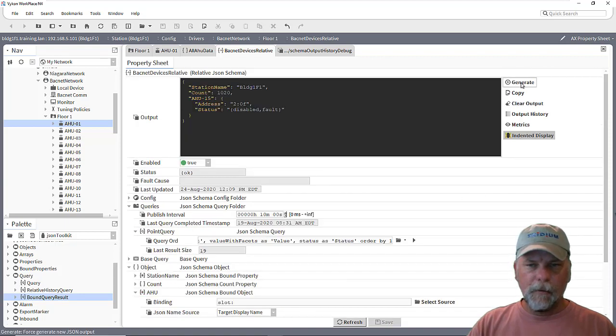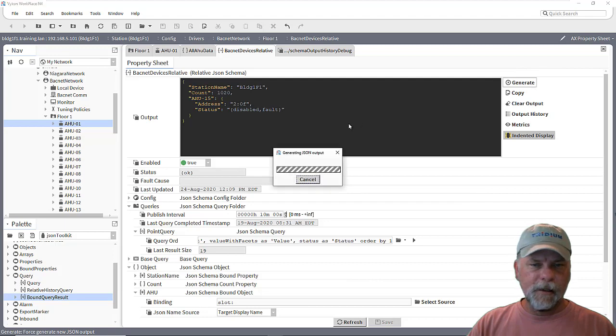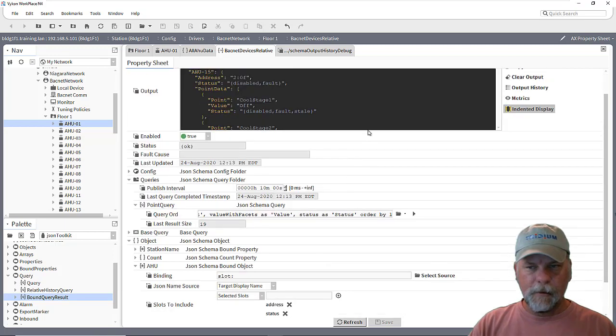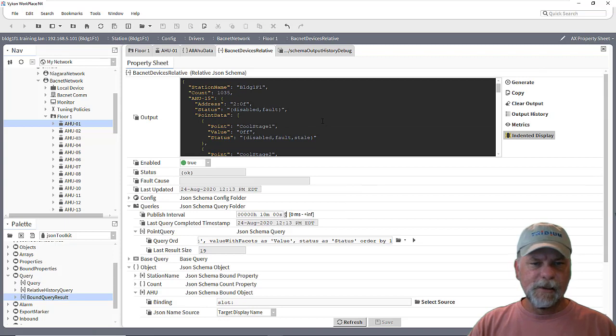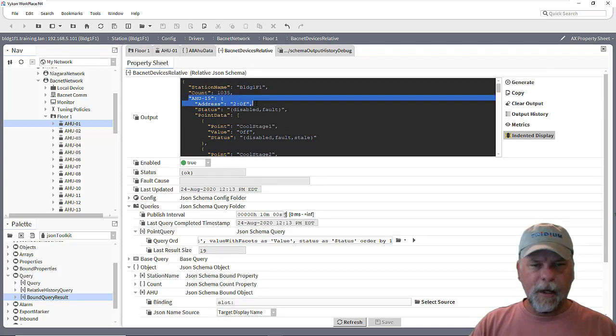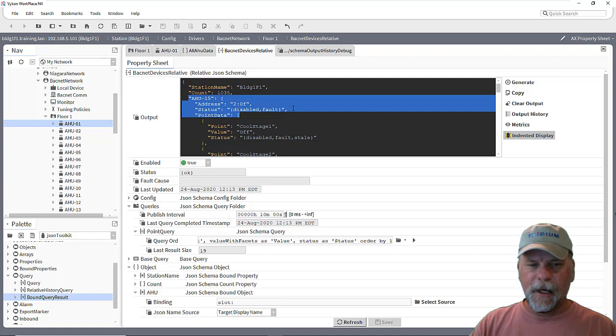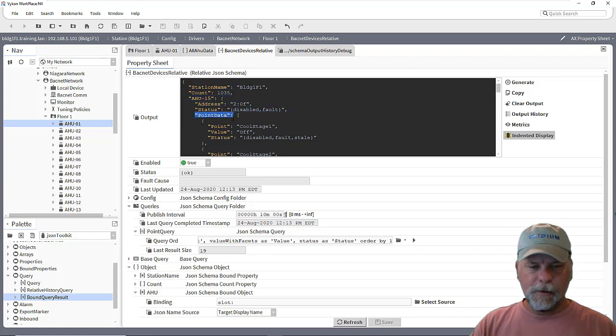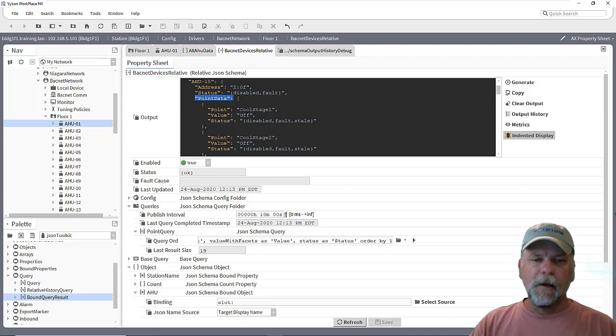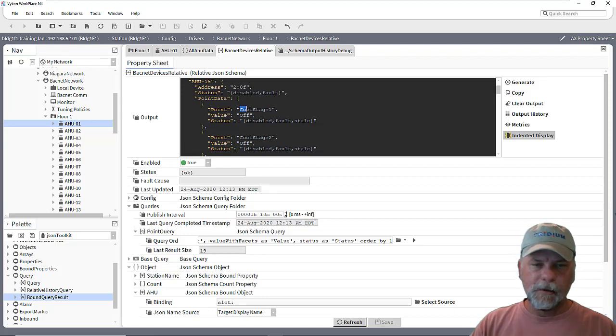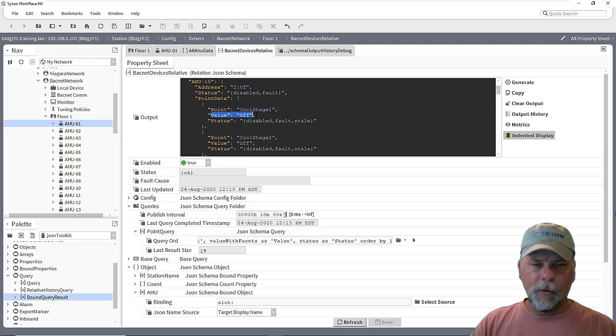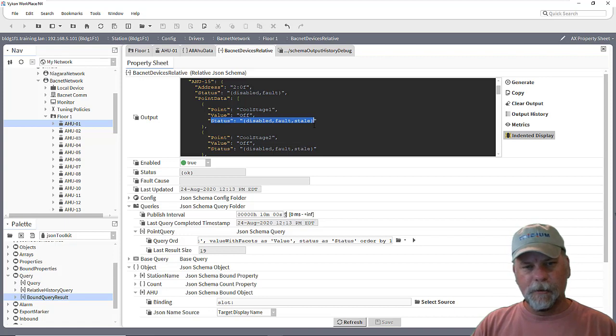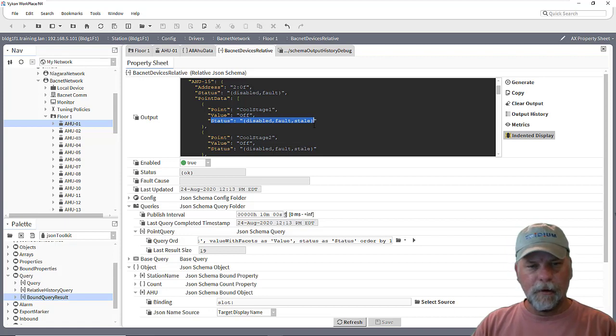And when we generate this then it'll go through for each of the 15 devices. And where before it was just displaying the name, the address, and the status, now I've told it to also display point data as an array which is the result of that query being run against it. And then we're going to see each of the that scheme of the BQL query, the projection. So they have the point name, the value of the point, and the status of the point.